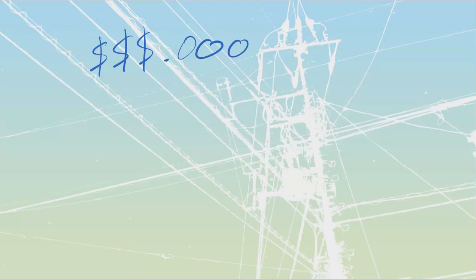because anytime that we're Meggering or doing high pot testing, we are going to values of voltage that are higher than what the system is rated for. If it's a 600 volt motor, I'm going to Megger that thing out at usually double, 1200 volts is what I'm going to be looking to Megger that thing out at. So you don't want that feeding back into the system, where all the other 600 volt components, particularly anything that is semiconductor, are going to be affected by it.